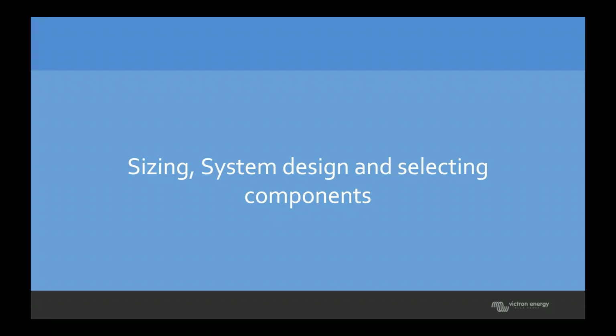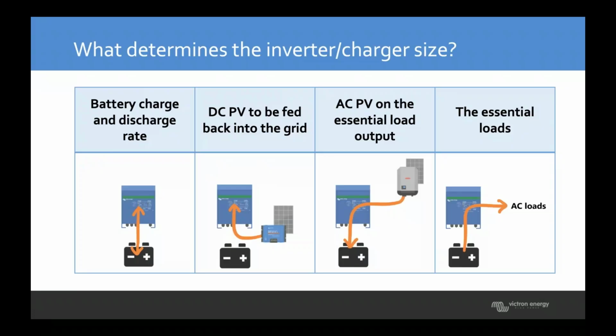So here are a few of the factors to determine inverter charger size. The battery's rate, how much you can discharge from a battery safely, and whether you want to feed any power back into the grid or not from the system. We can also feed back, if that's allowed in your area, from DC. So if there's surplus inverter or charger capacity, then it can convert DC PV back into AC sine wave, and that can be fed into the grid.